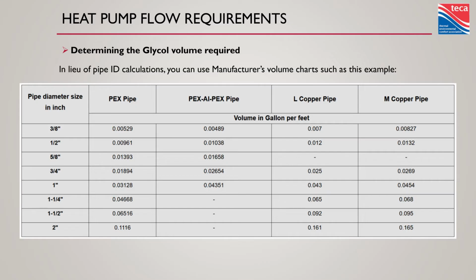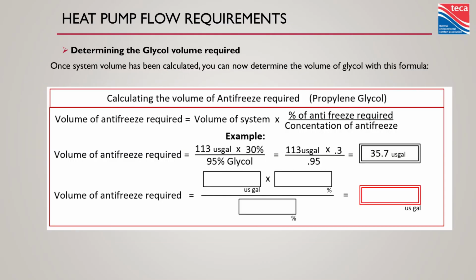An important thing to know about sizing glycol is how much fluid is in the system. So you're going to need to add it all up. I'm sorry, there's some software that can make it easier, or that's what they made apprentices for. Count up all the piping in the system, figure out how big it is, figure out how much volume's in there, and it's just a percentage of that. You don't usually buy glycol in 100% format, so then you apply the percentage that you're buying it in to figure out how much you need to buy. Usually it's 95% or 50-50. I try to buy more glycol than water because I don't like shipping water in buckets and paying someone to do that, but you never buy it 100%. So we've got some formulas in our workbook to figure out exactly how much glycol you're going to need to buy from your supplier.